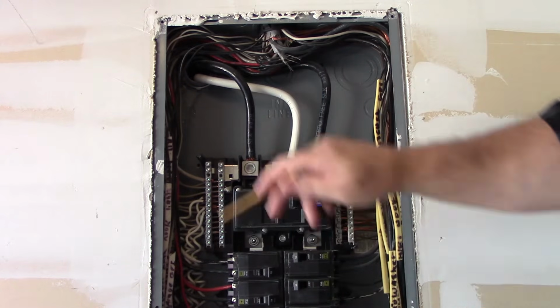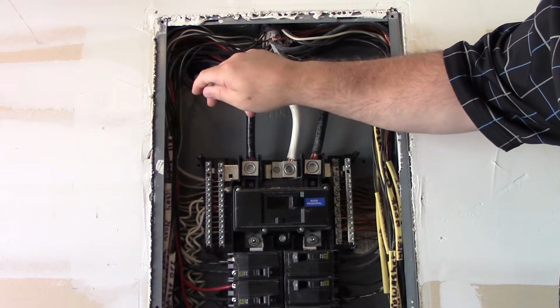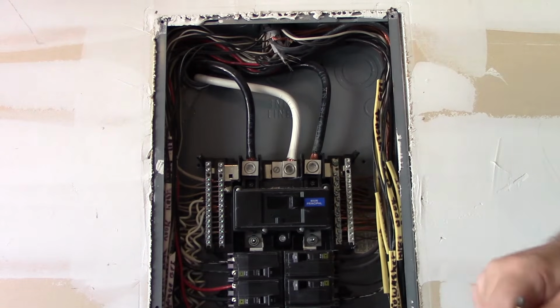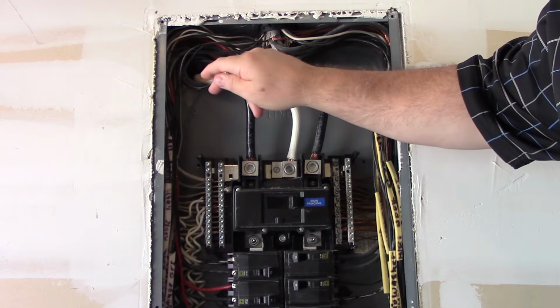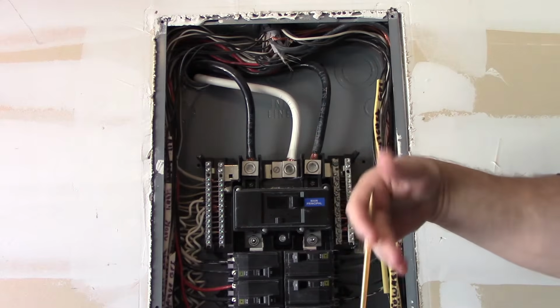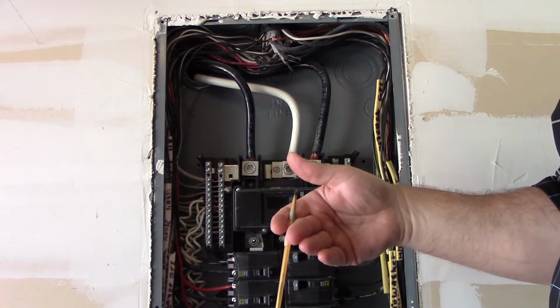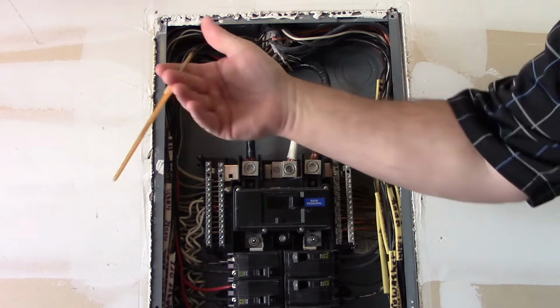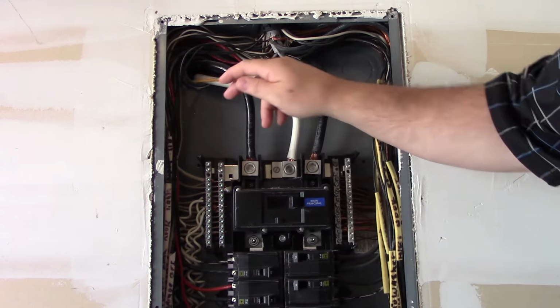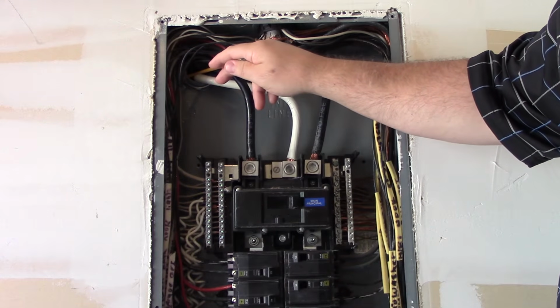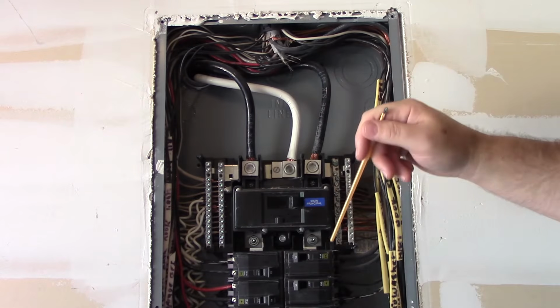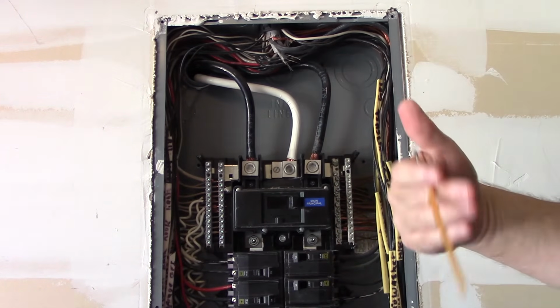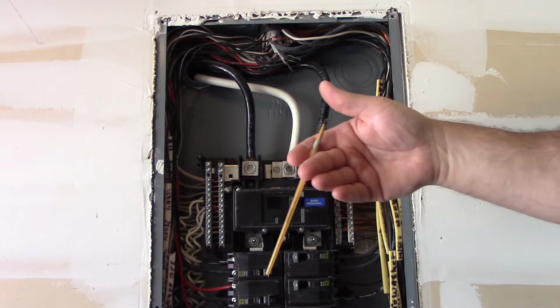Now, municipal guys, you're going to check this on the rough-in. You're going to make sure that they do that. Again, all right. Now, if this happened to be a metal nipple, then you're going to make sure you bond this nipple. You have to do it in accordance with the National Electrical Code in order to bond it at least on one end. Now, I can't see in the meter, so in this end, I would have a bonding bushing here, and I would have to make that connection here in order to bond this side in accordance with the service bonding and a surety aspect of it.